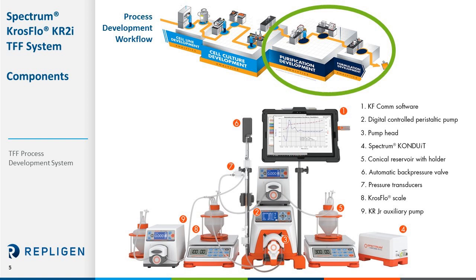The KR2i system was designed for downstream processing and can be used for UFDF application work associated with purification and formulation development, as shown in the process development workflow. The components of the KR2i system are depicted on this slide as the full suite of options and accessories available. The base system includes the main peristaltic pump drive and a Surface Pro tablet as the HMI with preloaded KFCOM software. Other add-on components include scales, up to two additional pumps, and the new KONDUiT device.